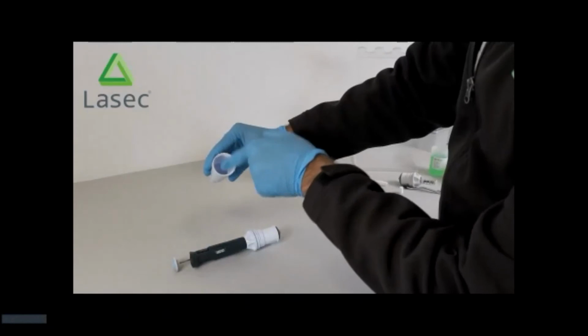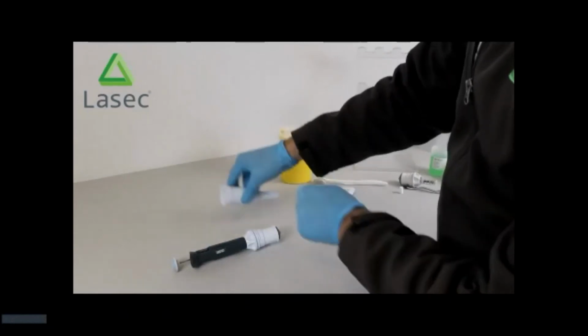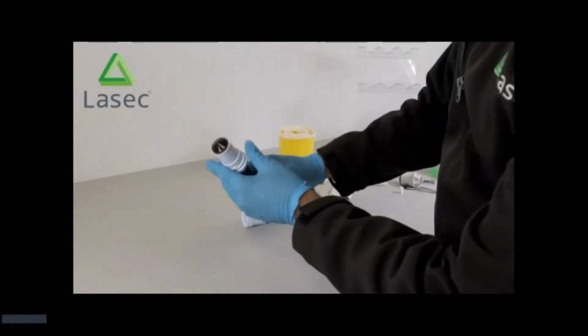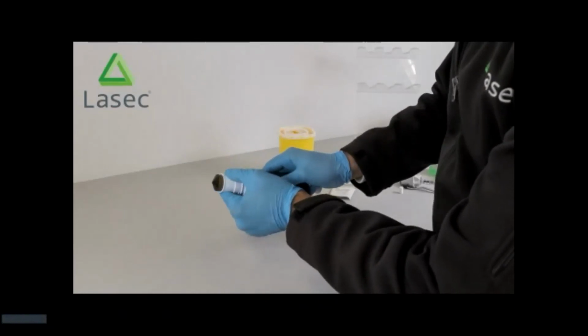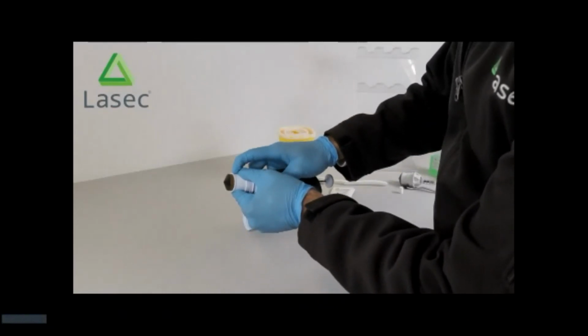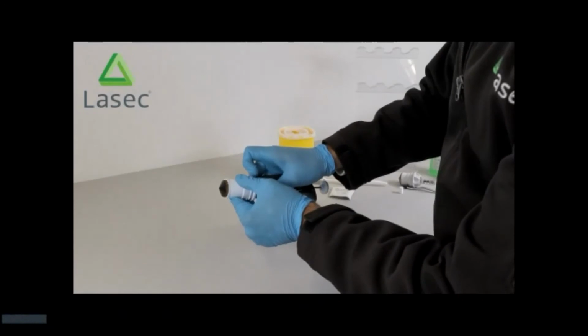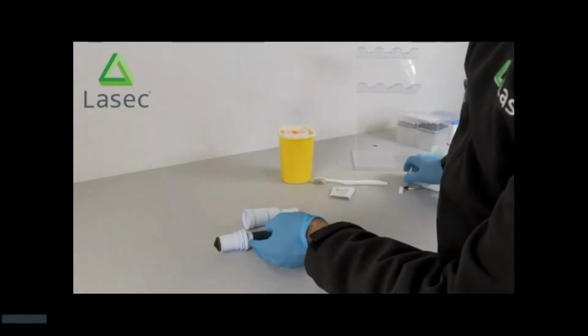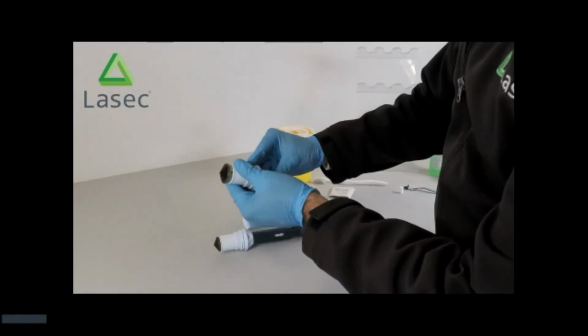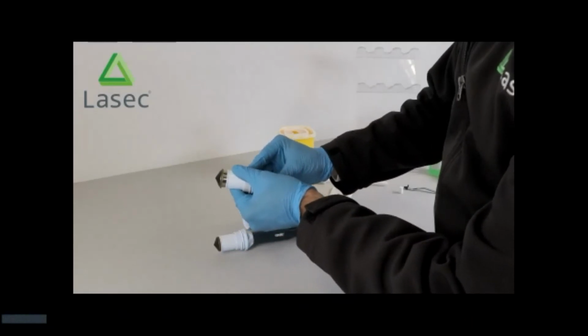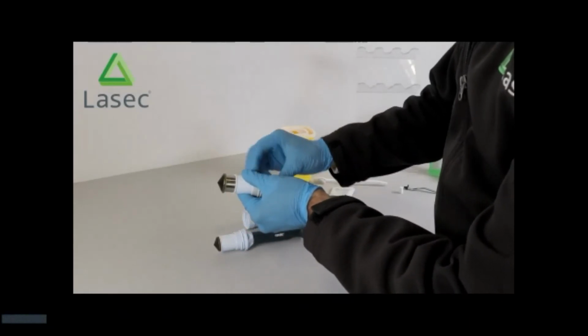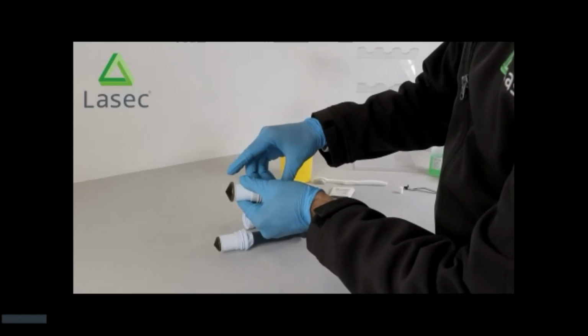That is because the filter that you saw at the beginning of this video was not fitted. So if you do have large volume pipettes in your lab, please go and check that the filter is actually fitted in the pipette. Like I said, the surface tension for large volumes in larger tips is not very high, so that liquid can move quite freely around. This is why we fit the filter into the pipette itself as a last barrier to prevent liquid from getting into those tip holders.